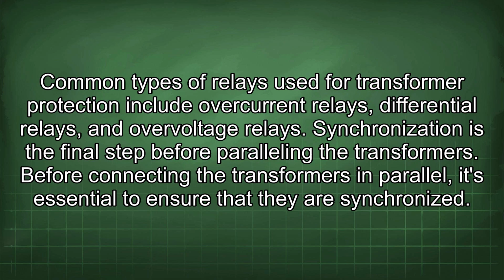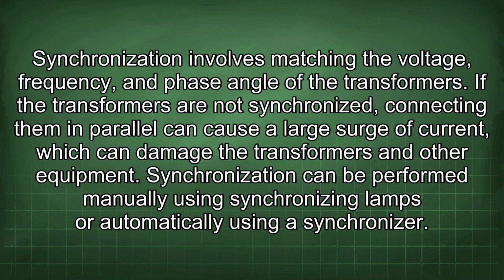Synchronization is the final step before paralleling the transformers. Before connecting the transformers in parallel, it's essential to ensure that they are synchronized. Synchronization involves matching the voltage, frequency, and phase angle of the transformers. If the transformers are not synchronized, connecting them in parallel can cause a large surge of current, which can damage the transformers and other equipment.